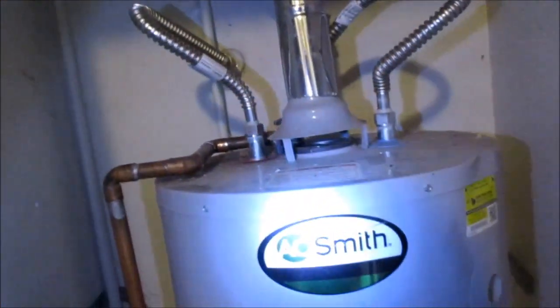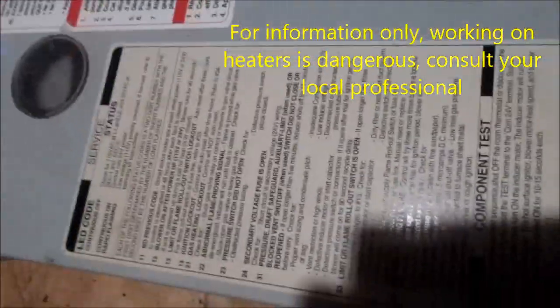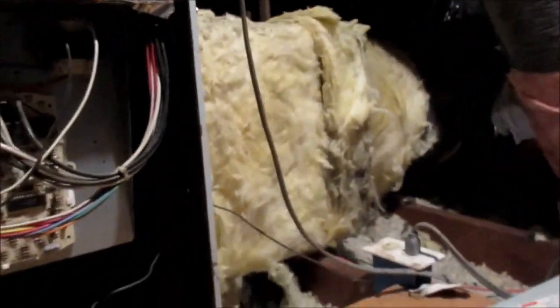A heater problem up there somewhere. You have a light, just stand on the water heater to get up there. Okay, so here's your code status light. We have red continuous light here and we have the door switch bypassed. This is a Bryant.